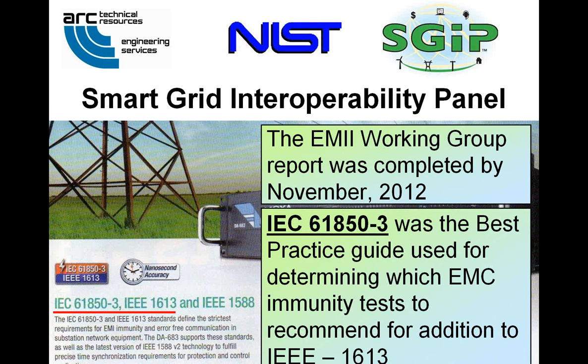IEC 61850-3, which was on the NIST Catalog of Standards, was the best practice guide that we used for determining which EMC tests to recommend for addition to IEEE 1613, which was coming up for renewal or amendment at that time. In addition, these 2 standards, 1613 and 61850-3, were already widely used in industry, as shown in their advertising.